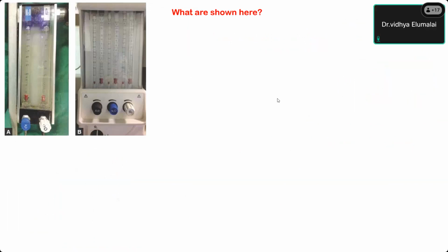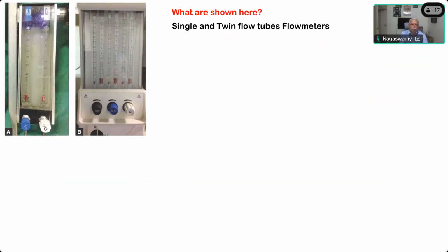For both low and high flow, A has only one flow meter, but B is a two tube system. A is a single flow tube meter, B is dual. They are called single and twin flow tube flow meters. So here there is only a single flow tube for both oxygen and nitrous oxide, whereas here you have one tube for low flow and another tube for high flow for oxygen. Similarly for nitrous oxide and medical air, you have two flow tubes.